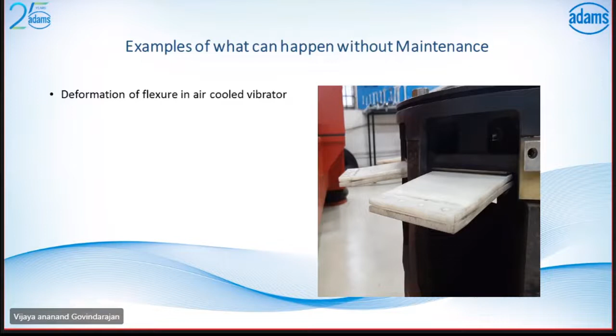These flexures are polypropylene flexures, so they need to be removed and refitted over a period of time. If it is not maintained properly, that may ultimately result in some other part damage. Yes, that will cause damage to the shaft. The shaft is a hollow cylindrical shaft made of steel. This guides the shaker at the bottom through a linear ball bearing. We need to give proper torque to the flexures and engage the armature at the intact position. If cross-axial movement due to offset loading or improper maintenance happens, this kind of damage may cause damage to the bearing as well as the shaft.